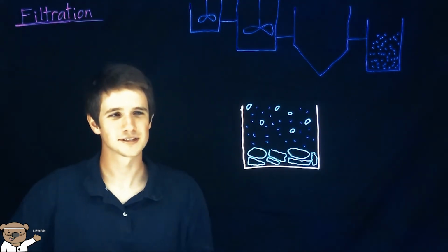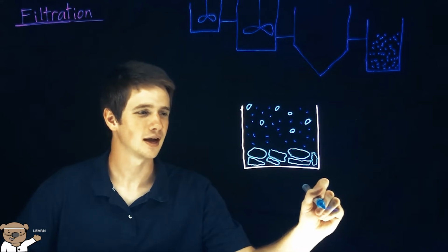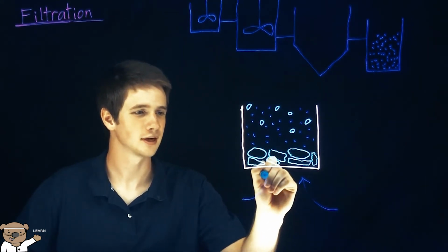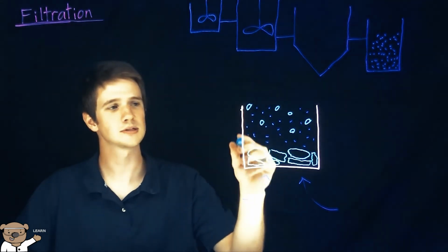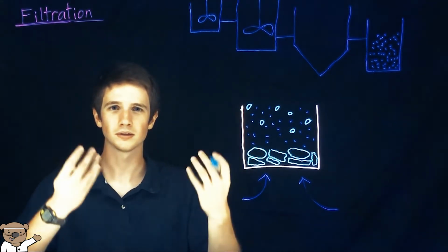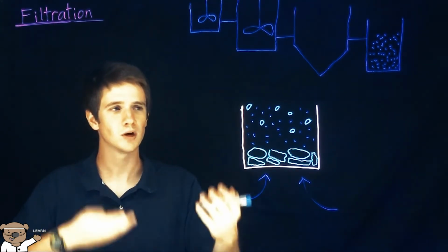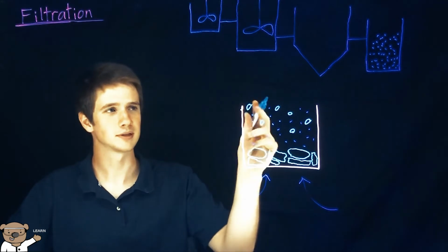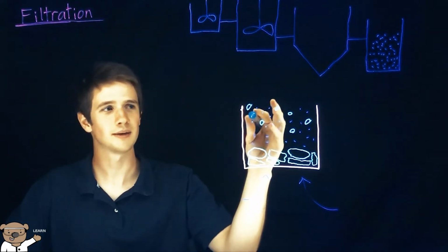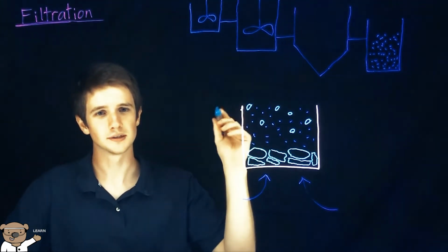These sand filters need to be cleaned sometimes, however. This is done by running water the opposite direction from the bottom of the filter up towards the top. This loosens all of that sand and coal so that all of the dirt particles and whatever else was caught in the filter gets washed out from the bottom to the top.